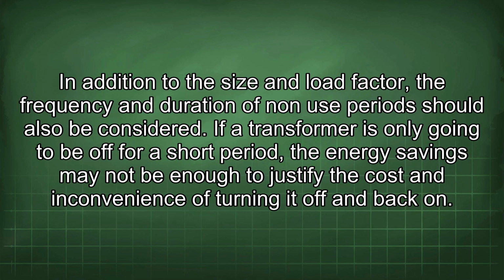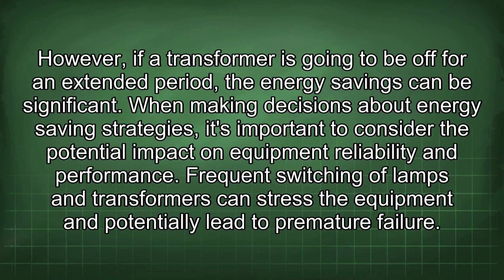In addition to the size and load factor, the frequency and duration of non-use periods should also be considered. If a transformer is only going to be off for a short period, the energy savings may not be enough to justify the cost and inconvenience of turning it off and back on. However, if a transformer is going to be off for an extended period, the energy savings can be significant.